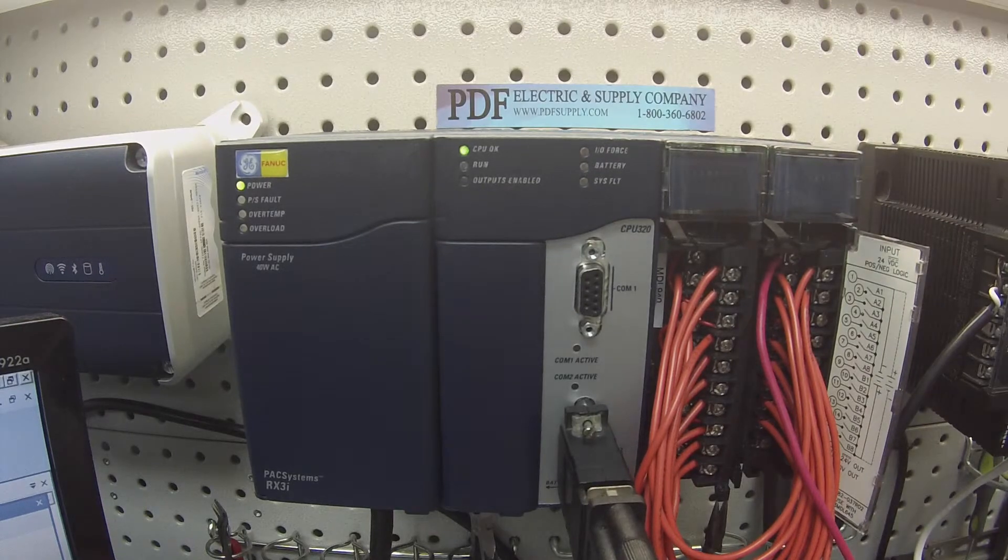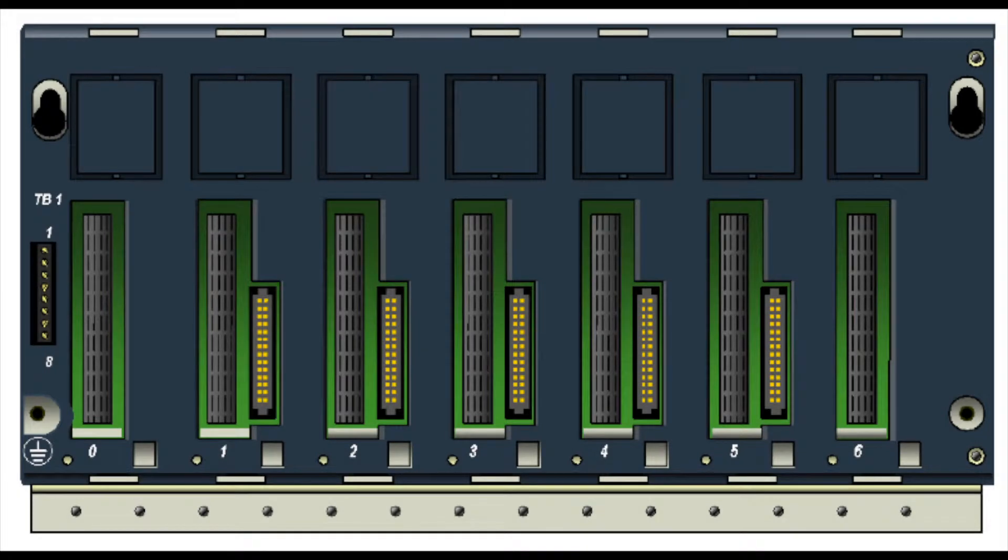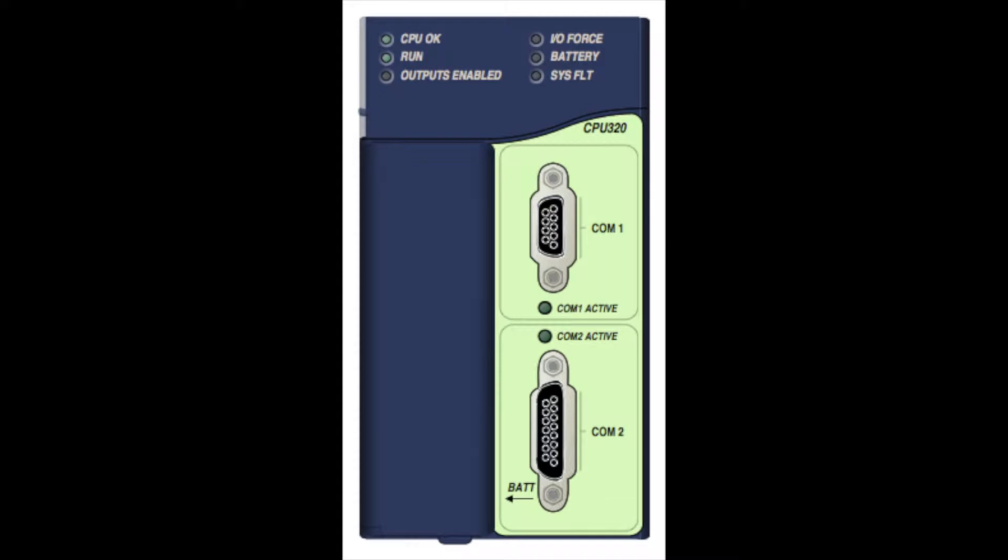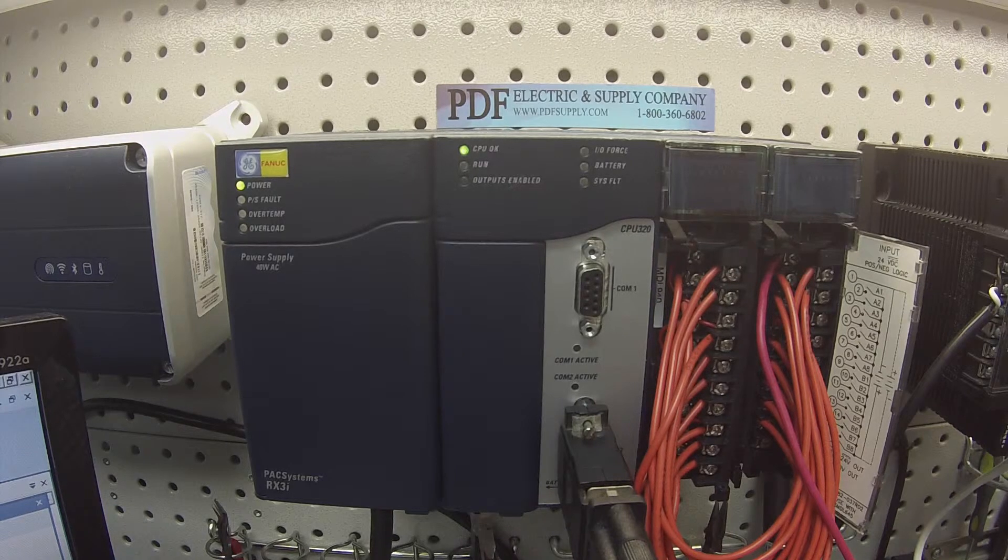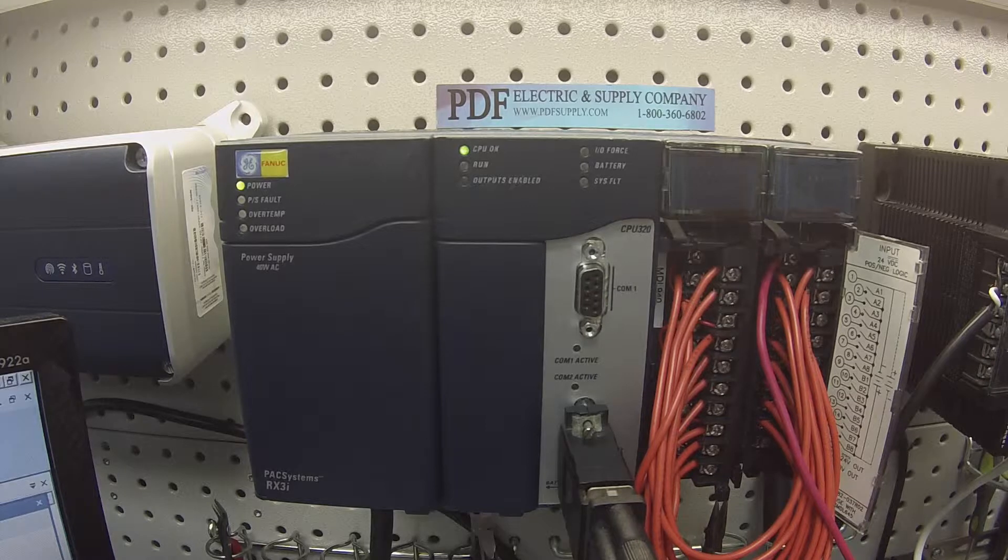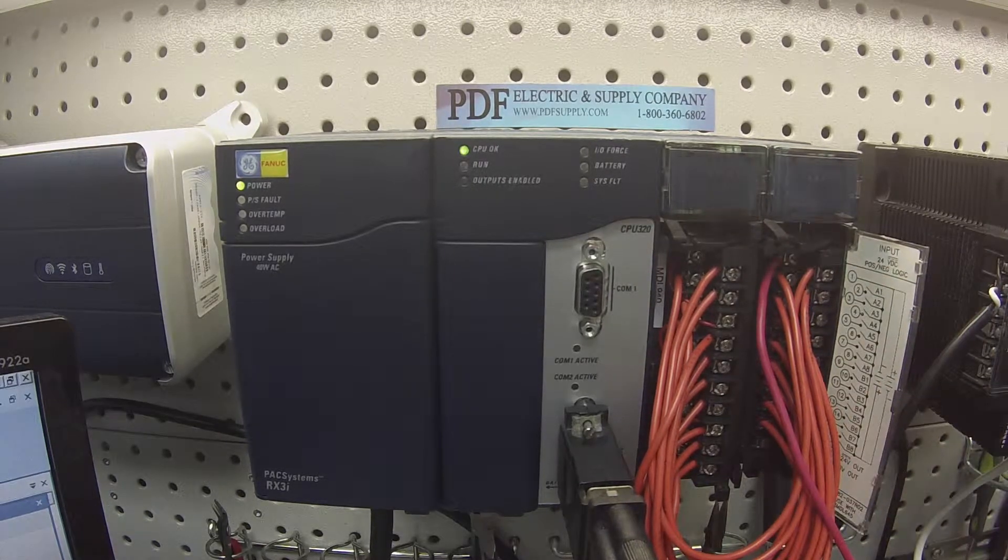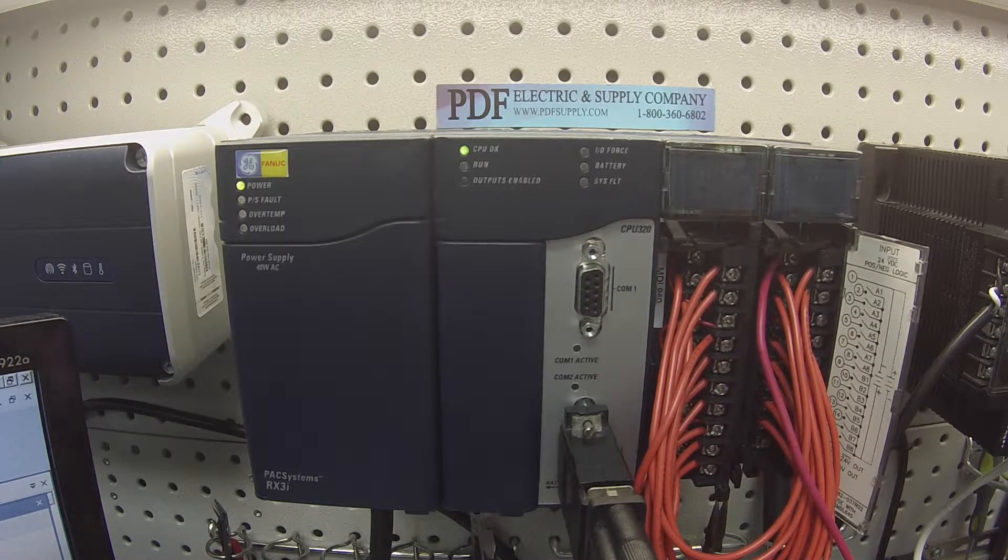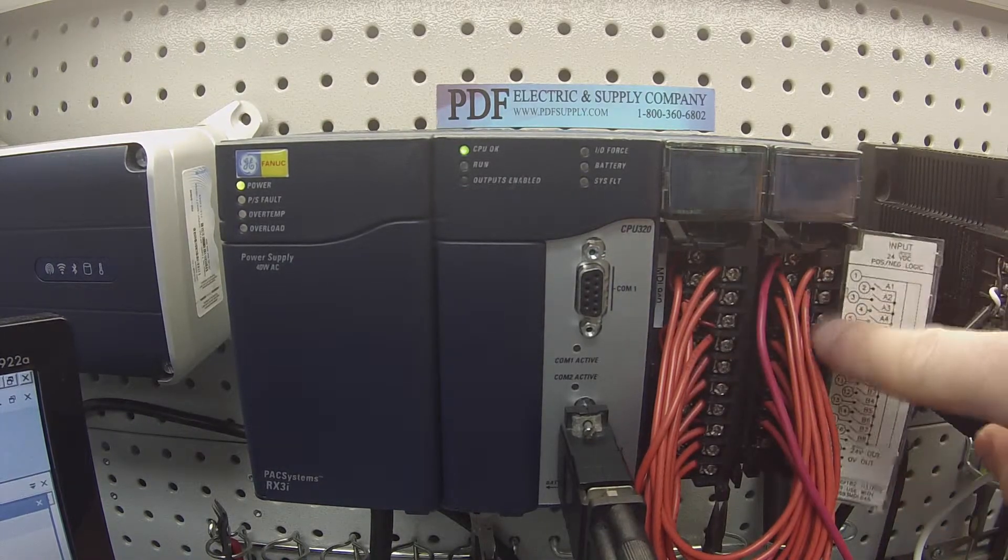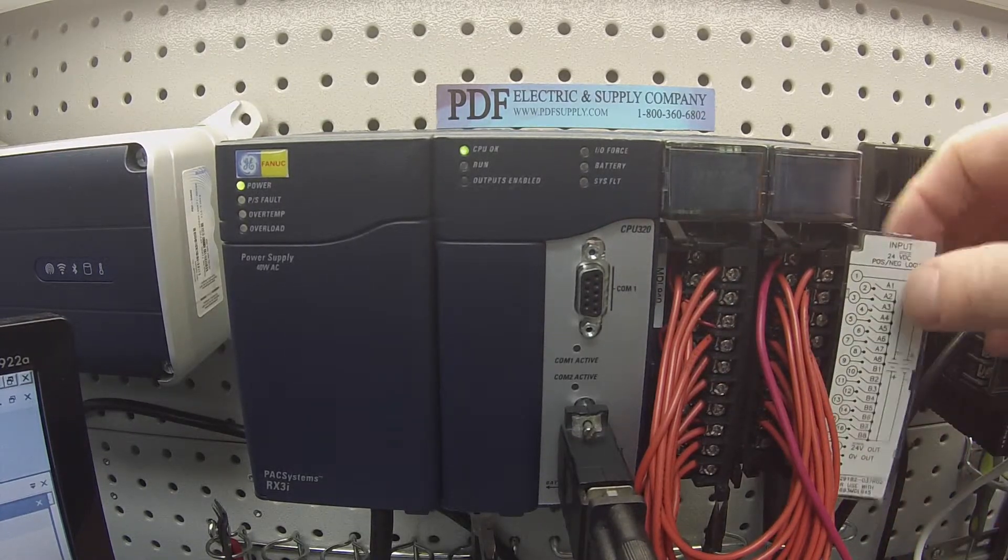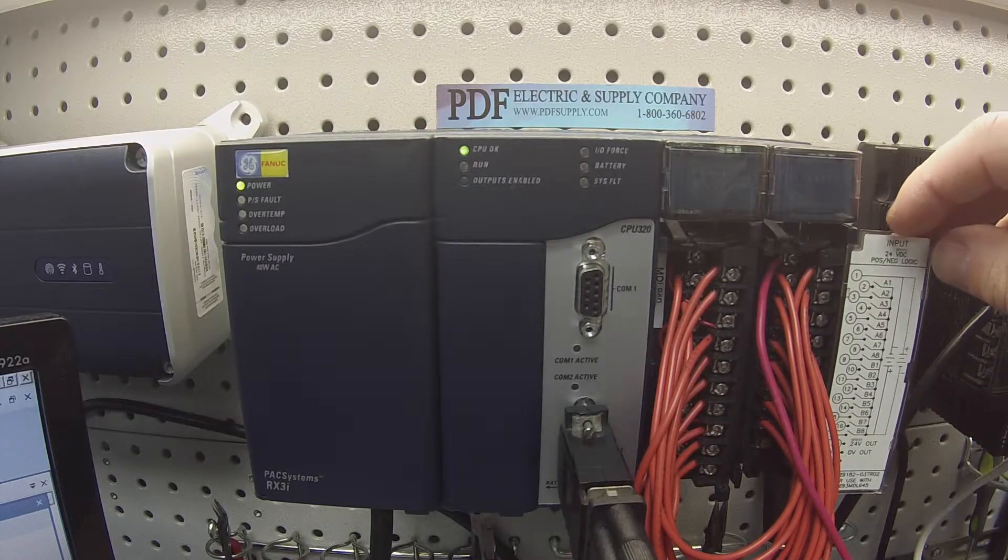What I have in front of you besides that is the IC695CHS007 seven-slot rack, an IC695PSA040 power supply, and the processor I'm using for this test is an IC695CPU320. Other peripheral devices that I'm using for this test is a 24 volt DC power supply. If you are using, as you can see I have a preset terminal strip where the outputs go to the corresponding inputs, meaning output one goes to input one, output two goes to input two and so on, as per the wiring diagrams on the MDL940s and MDL645 or 646.